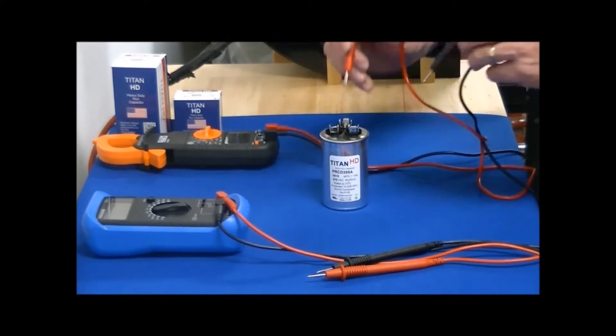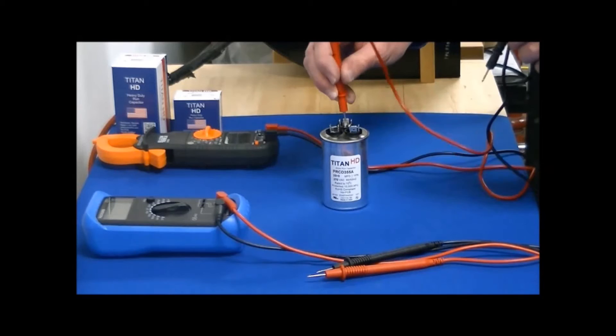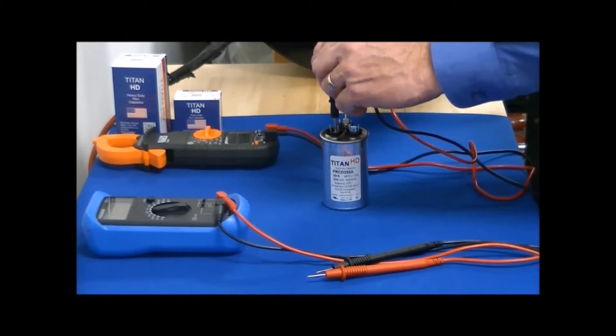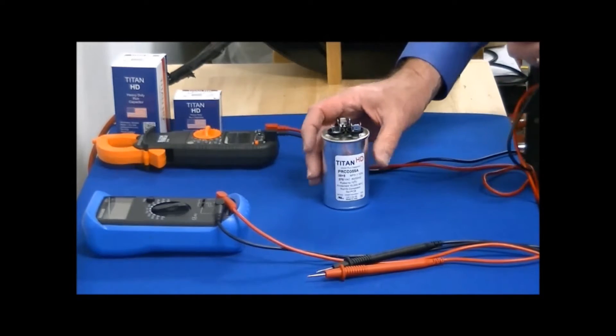Then do the same thing for the fan side. One probe on common, one probe on fan. That will give us the microfarad reading for the fan side, which is 5.07 microfarads. Both are well within tolerance.